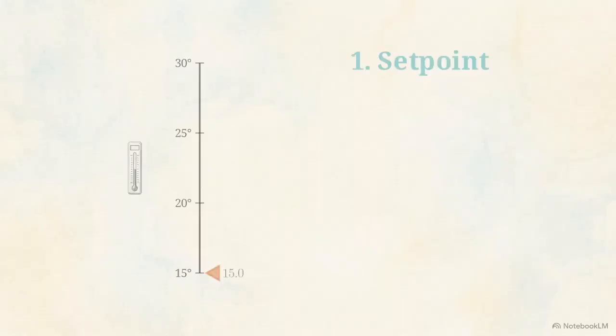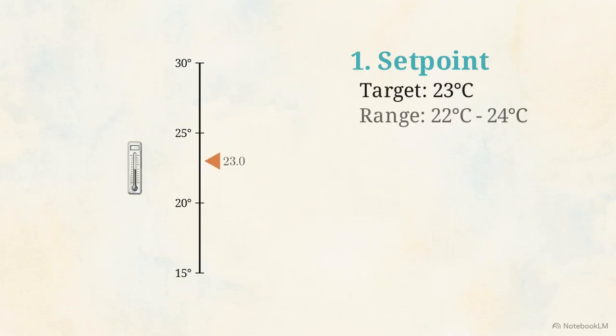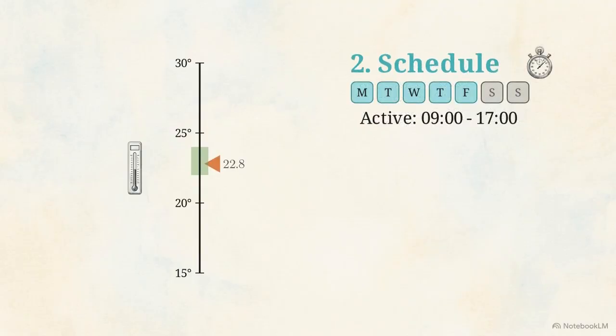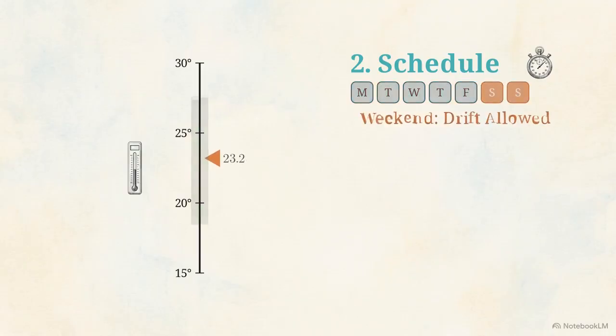The first boundary is a set point. This is the specific numerical target the controller tries to reach. It is usually configured as a range, like 22 to 24 degrees, to prevent the equipment from constantly flickering on and off around a single degree. The second boundary is a schedule. This time constraint dictates when the set point actually matters, say 9 to 5 on weekdays, and when the building's temperature is allowed to naturally drift.